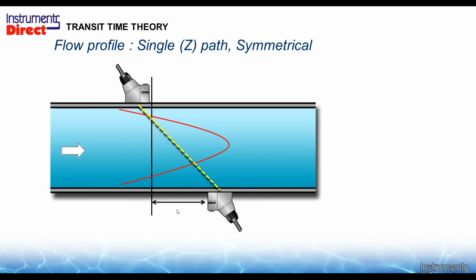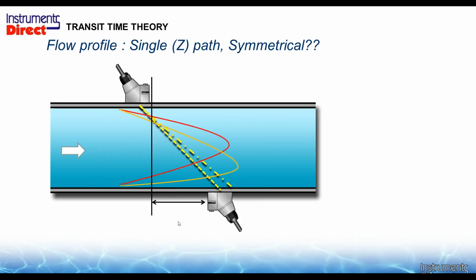Now, what if I don't have enough straight run of pipe? If I don't have enough straight run of pipe, my flow profile might be distorted. And if my flow profile is distorted enough, my sensor may not even see this signal over here. And if that is the case, I may actually have to do something which is called profiling the application, which is where I will have to move the sensor to find the sweet spot. Now, this should only occur in applications where I don't have the required straight run of pipe.